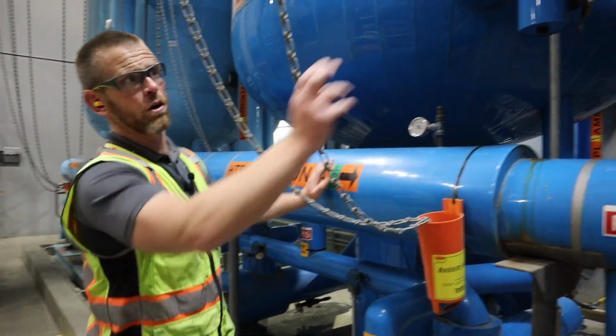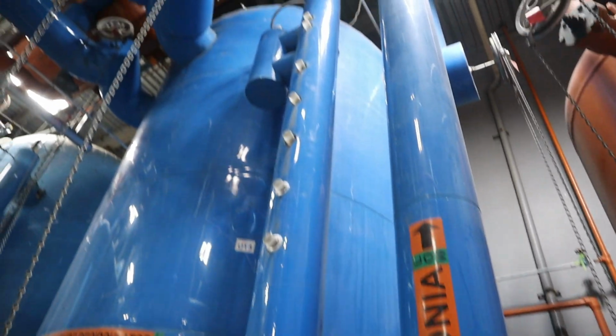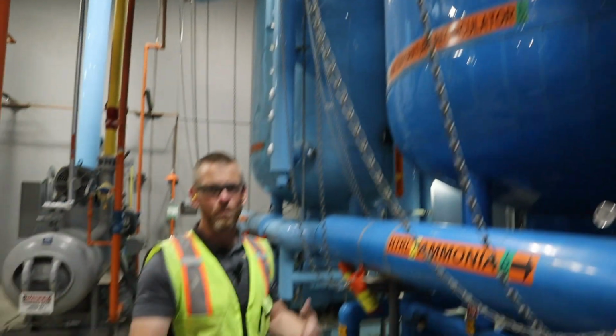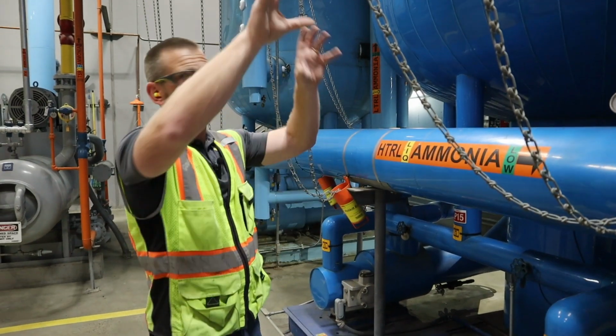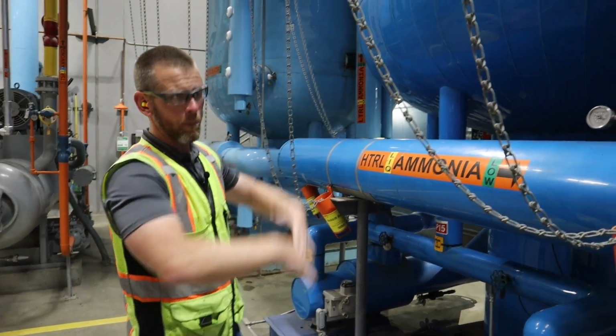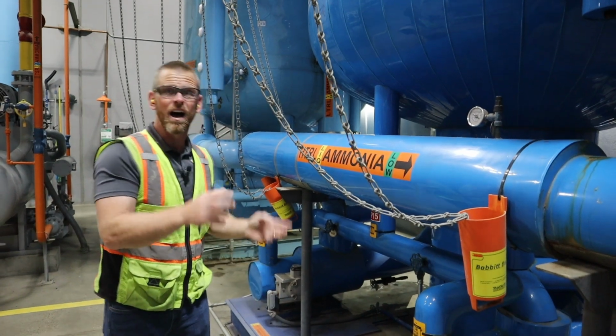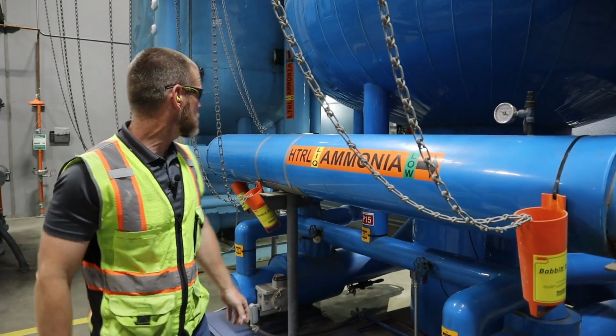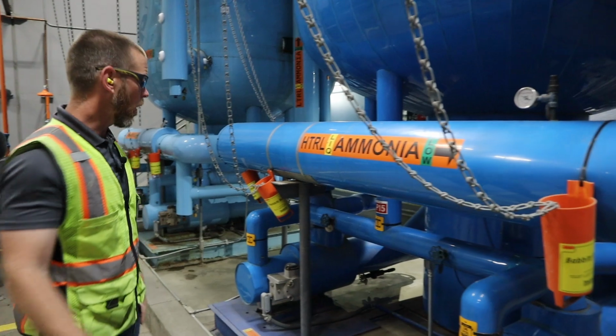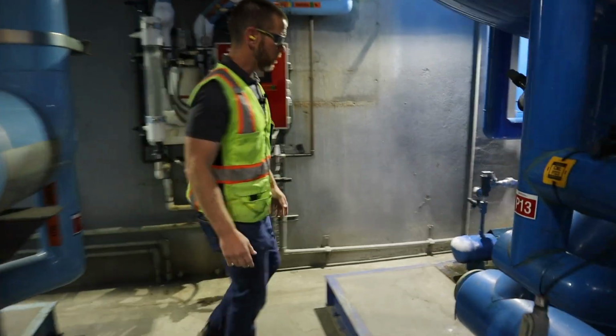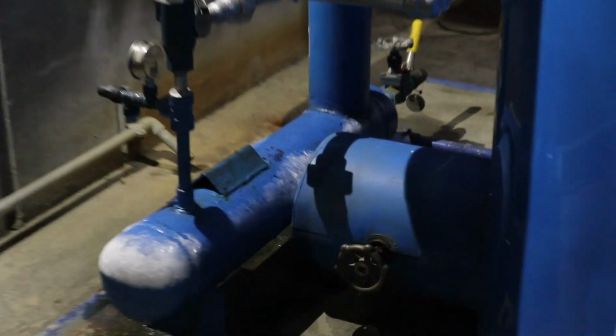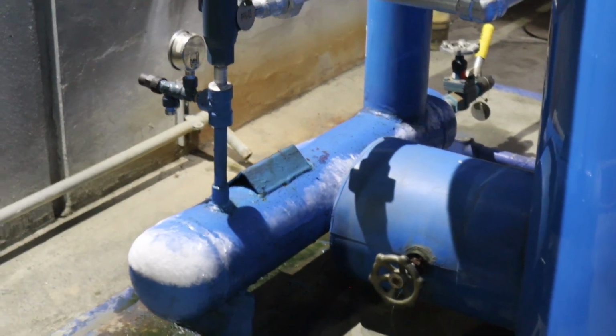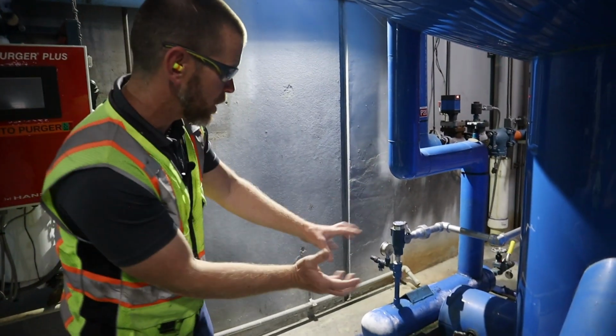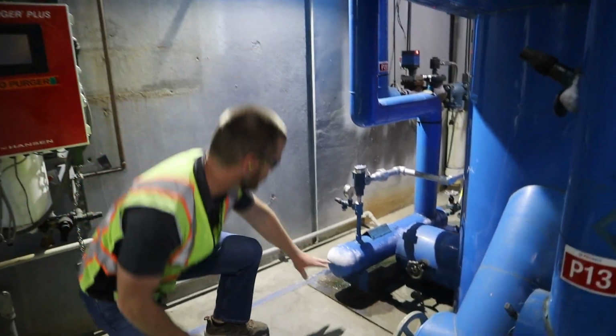So our high temp recirc liquid line pumps to the evaporators, and then wet suction, which is called high temp recirc suction, is piped back to the recirculator, where any liquid droplets fall to the bottom and are resupplied to the pump. Vapor goes to the top and is fed to the high stage compressors. If you follow me this way, I'll point out a couple more things about the recirculator. You'll almost always see an oil pot on a recirculator. It'll be installed at the low point. The oil is heavier than the ammonia, drops to the bottom and is allowed to drain into the pot. And you can track the oil level by looking at the frost line on that pot and know when oil needs to be drained.